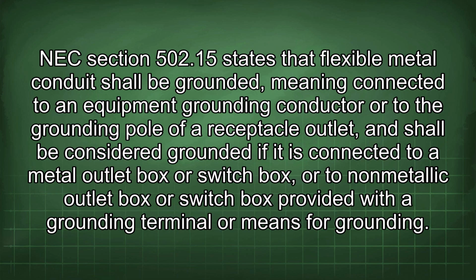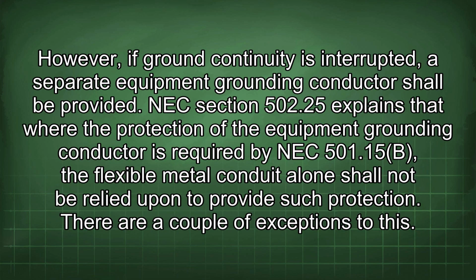NEC Section 502.15 states that flexible metal conduit shall be grounded, meaning connected to an equipment grounding conductor or to the grounding pole of a receptacle outlet, and shall be considered grounded if it is connected to a metal outlet box or switch box, or to a nonmetallic outlet box or switch box provided with a grounding terminal or means for grounding. However, if ground continuity is interrupted, a separate equipment grounding conductor shall be provided.